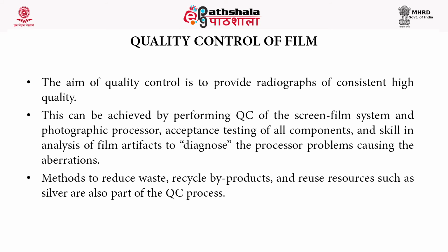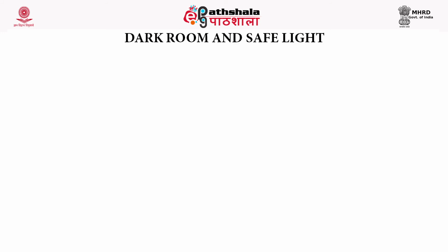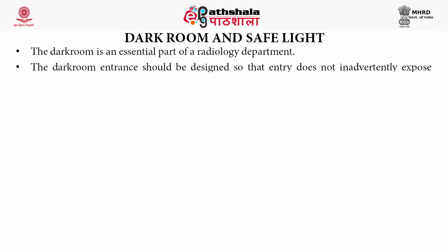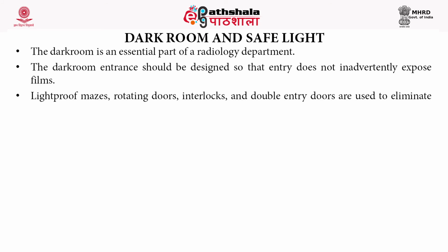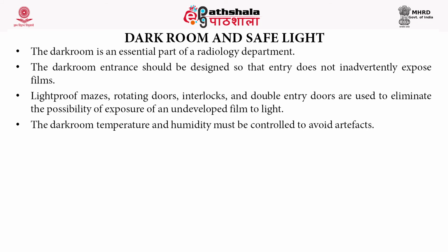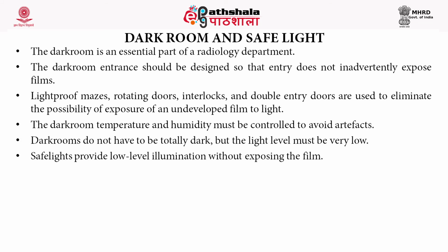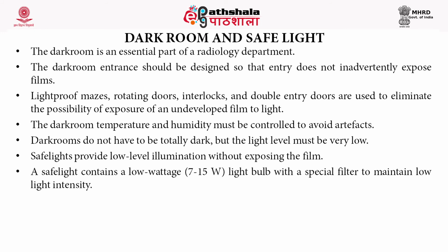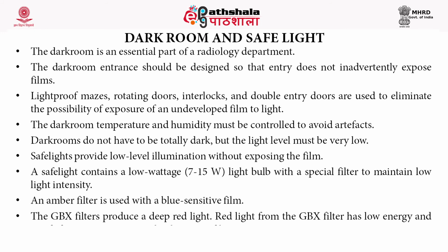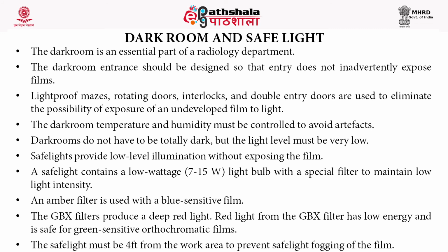In the field of radiography, we must understand what is the safe light needed for the development of a film and what is the concept behind the dark room. The dark room is an essential part of a radiology department. The dark room entrance should be designed so that entry does not inadvertently expose films. Light-proof mazes, rotating doors, interlocks and double entry doors are used to eliminate the possibility of exposure of an undeveloped film to light. The darkroom temperature and humidity must be controlled to avoid artifacts.